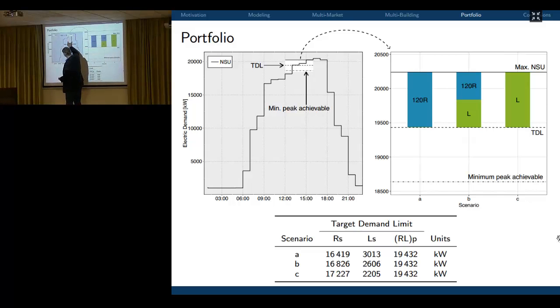During those hours, from 12 to 4, that's when I observe my target demand limit — that's why I showed this white block here. If I pre-cooled all of the buildings in the portfolio, I could get down to this minimum line, the lowest I could pre-cool. And if I don't do anything, I'd have this upper value — that's the standard control with no pre-cooling or change to the control, which I call night setup control, NSU.